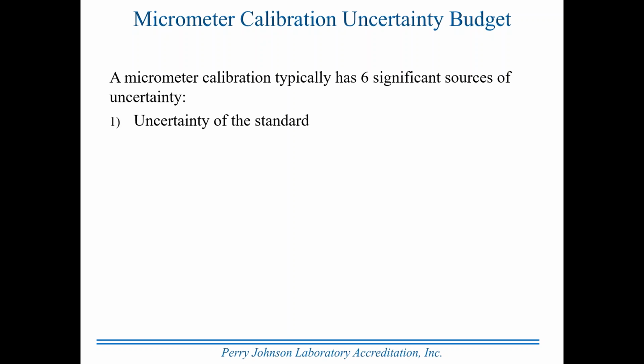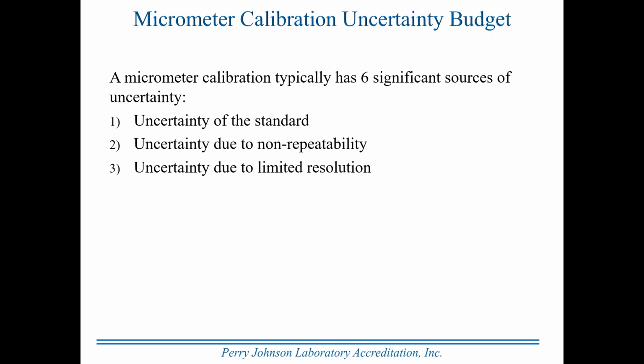The very first source that we want to consider is the uncertainty of the standard used to calibrate the micrometer. Then we want to look at uncertainty due to non-repeatability. Now remember, you may see this term as repeatability, the uncertainty of repeatability. It's actually the uncertainty of the non-repeatability, or inability of the device to repeat a reading. Uncertainty due to limited resolution. We talked some about what that resolution might be. We're looking here with a micrometer to have a fairly small resolution, which means it can discriminate between very small differences on two different items. So if you took two supposedly identical components and wanted to measure a dimension on them, the micrometer has to have enough resolution that it can detect a difference in size between the two within the specification for that dimension.